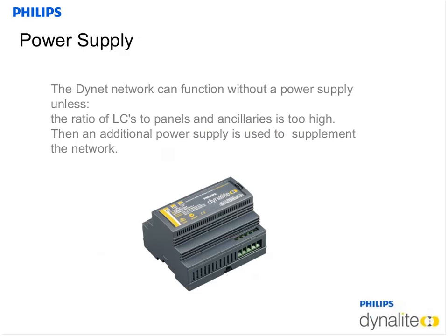Power supply. Well, I mentioned a power supply probably because you don't actually need one. You don't need one because each of the main load controllers in a Dynalite network generates its own power onto the network. So a straightforward Dynalite network in an office, perhaps in a factory even, where you simply have your load controllers, perhaps some sensors, a couple of keypads, a couple of panels, you probably don't need a power supply.